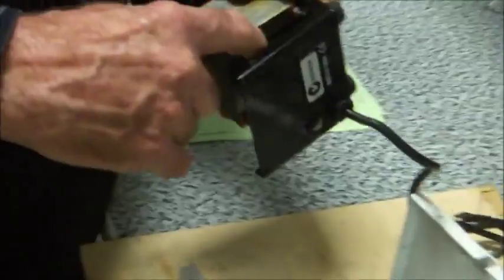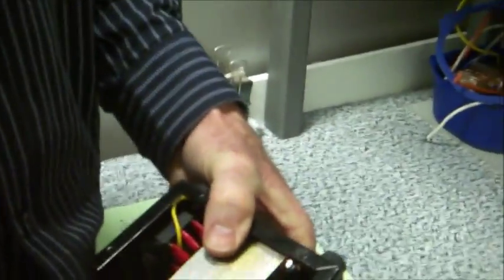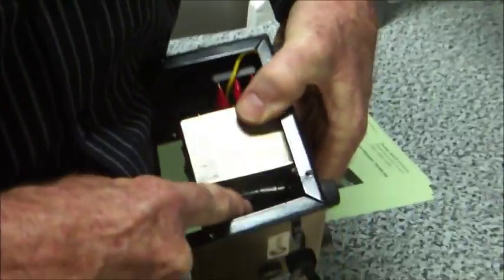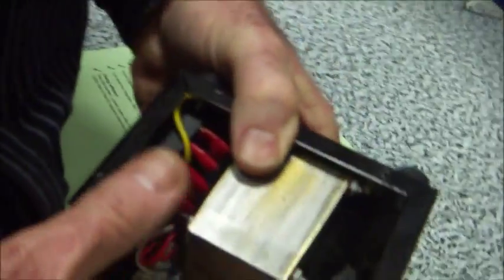The other thing I want to point out on the EI transformer is that the primary and the secondary in here are not divided, it's not on a divided bobbin, it's on a concentric bobbin. So that isn't as safe as on a divided bobbin. Here, divided bobbin.